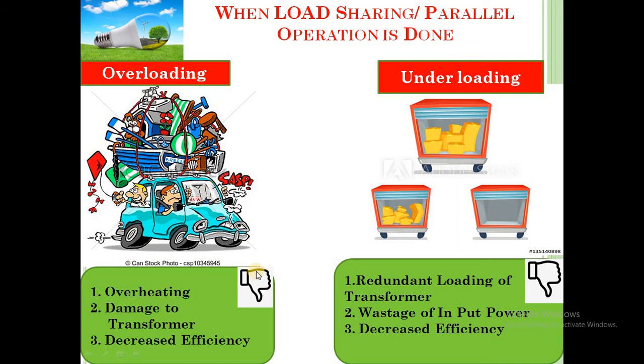So because of the overloading, what will happen? Overheating of the transformer will occur, damage to the transformer will occur, and there will be a decreased efficiency of the transformer. Now the second case is underloading. Here I have taken three images, in which two images are of underloading and one image is of no loading. So what will happen in underloading? Redundant loading of the transformer will be done.